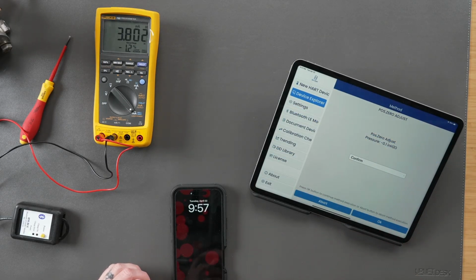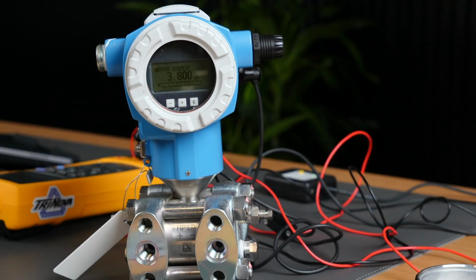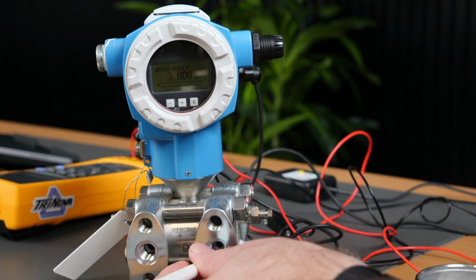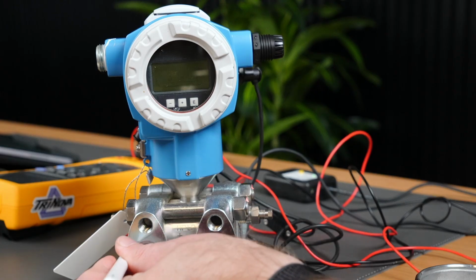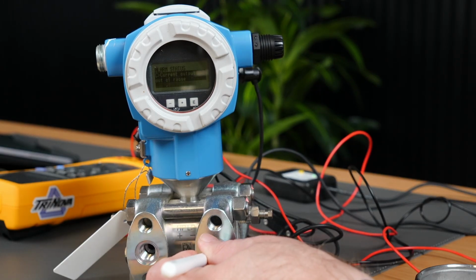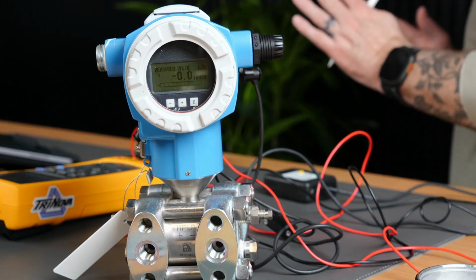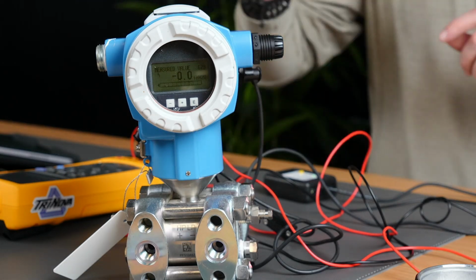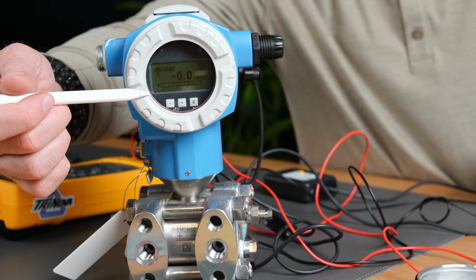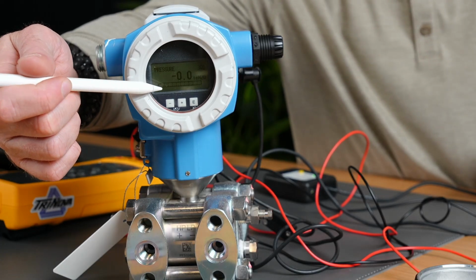All it's doing is comparing the pressure I feel here versus the pressure I feel here, and we're going to make it zero. It's zero in that device, high side to low side. So right now we're seeing 0 inches of water column pressure being shown here.